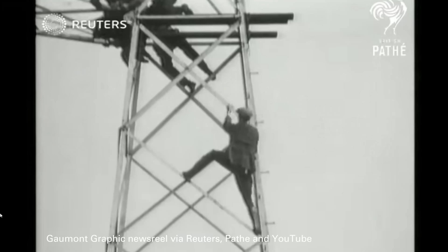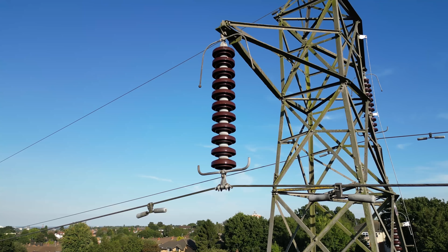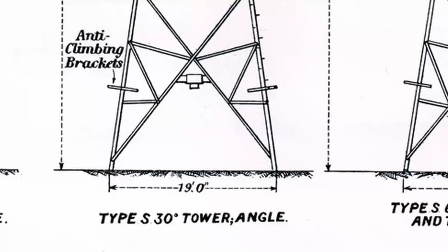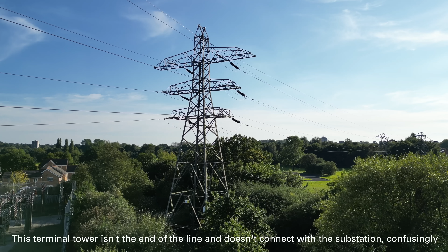Unusually, these first pylons, later known as PL1s, came in single or double circuit versions, one circuit being a set of 3 conductors, with the grid being 3-phase thanks to Nikola Tesla. Strings of ceramic insulator discs attach the high voltage conductors to the towers. Where the conductor changes direction or ends, the insulator is near horizontal, under the tension of the conductor. Hanging loops of jumper cable connect the different sections. Because of this sideways force, stronger deviation towers are required at corners, with several different sizes of pylon used depending on the angle of the corner.